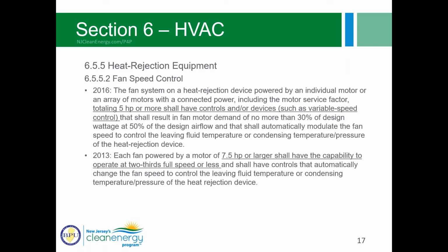All right, so moving on to heat rejection equipment, looking at the fan speed control. This is the full language from both 2016 and 2013. Basically, if the condenser tower fluid cooler has 5 or more horsepower of fan motor, whether it's a single fan or multiple, the fan speed needs to vary. In 2013, it only applied to motors that were 7.5 horsepower or larger. The exceptions are condenser fans serving multiple refrigerant or fluid cooling circuits, and condenser fans serving flooded condensers. So it's a slight update, in that it's the total connected motor horsepower that is being evaluated rather than just the single motor.